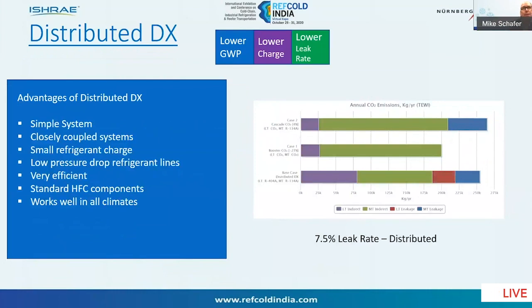So the advantages of a distributed system, once again, employing the strategies we talked about: very simple system, very closely coupled systems, which results in a very small refrigerant charge. Given the short length of runs, there's lower parasitic losses due to the pressure drop in refrigerant lines. And generally, these systems are very efficient. You can use standard HFC components, and it works well in all environments, all climates.